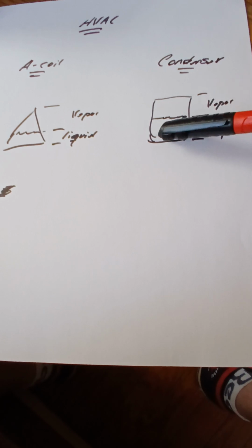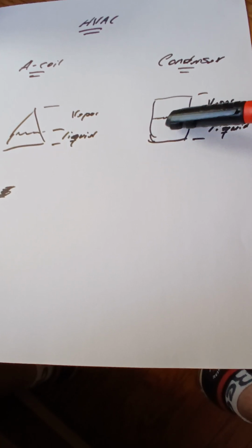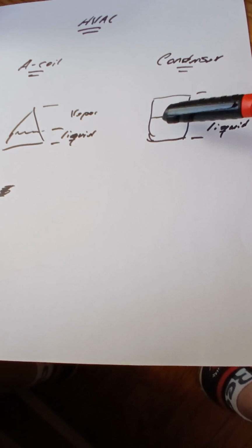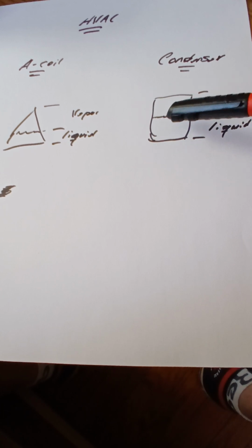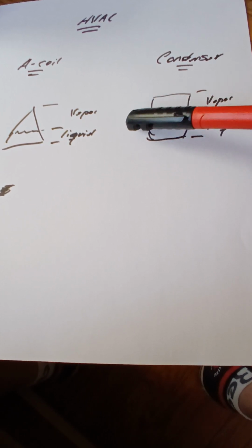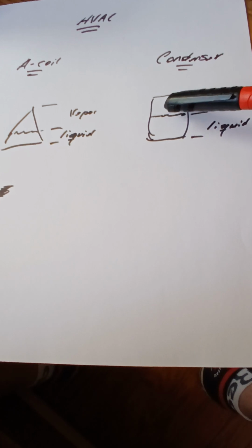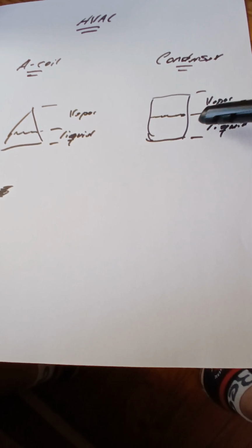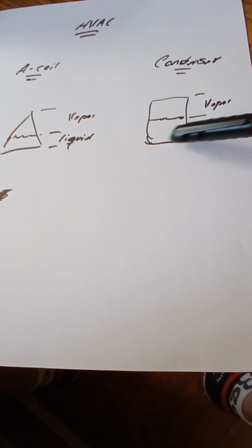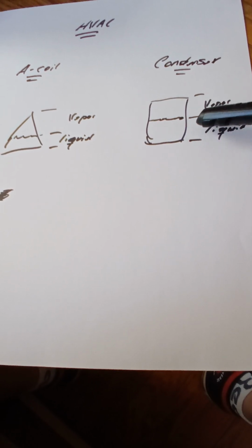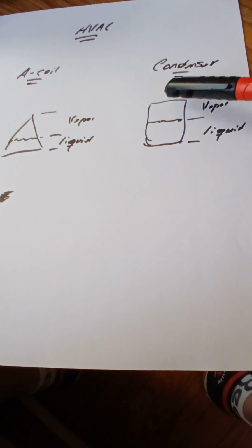Goes over here. You have a compressor in your condenser, so the compressor has to be working. The compressor does not need to have liquid refrigerant running through it. It needs vapor. So it comes in here as vapor, then it compresses it. Then it's a high pressure vapor. There's a condenser fan motor that sits on the top and pulls air into the sides. This is another reason not to plant bushes and whatnot around this. So it sucks air in here, then it dissipates the heat here.